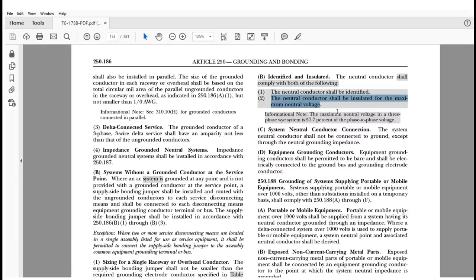So many of the medium voltage systems that operate in the 2.4 to 15,000 volt ranges are either a low resistance ground or a high resistance ground. Really the only difference in those is the value of the resistor, okay? And it controls the amount of ground fault current that's permitted during a ground fault event. And the only other common one is what's called a solidly grounded system, which is the more common when you're dealing with medium voltages above 15 kV. They're typically going to be solidly grounded, or they're going to be just de facto ungrounded type systems, okay?